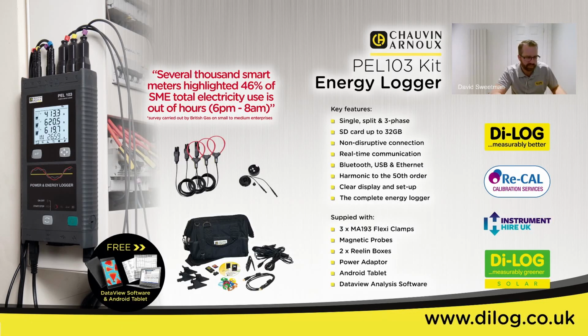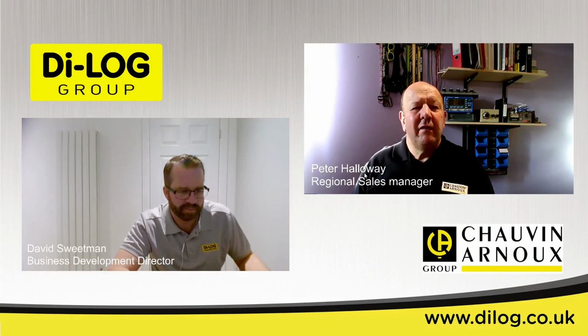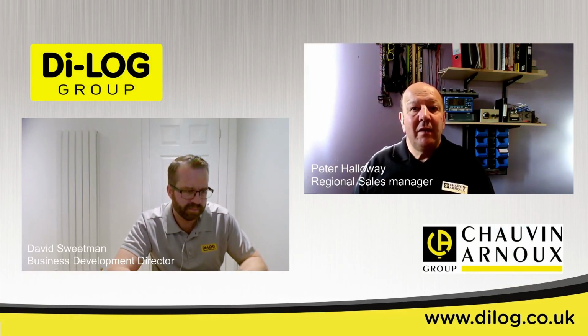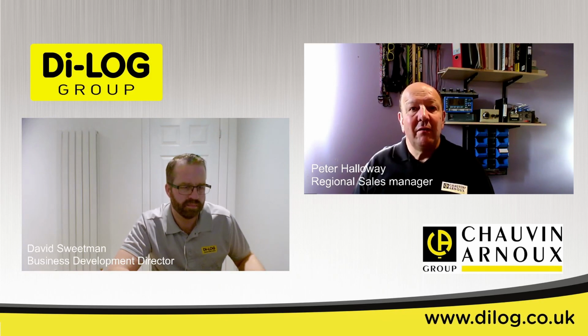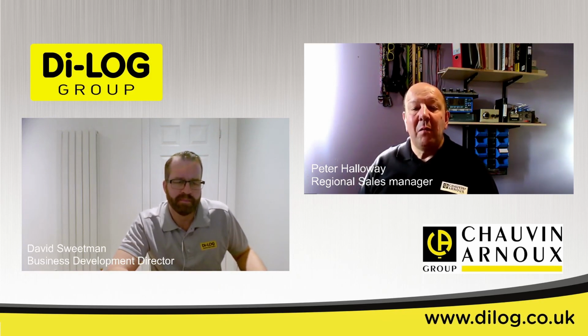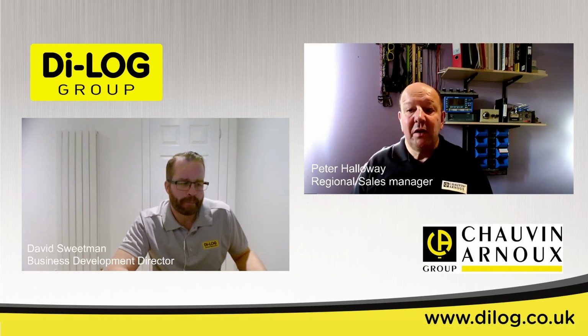No, just about the power adapter itself - I think it's rated to 750 volts, so even if you've got phase to phase, it's still going to power the instrument. The instrument itself needs 230 volts, but that's all taken care of by the power adapter.